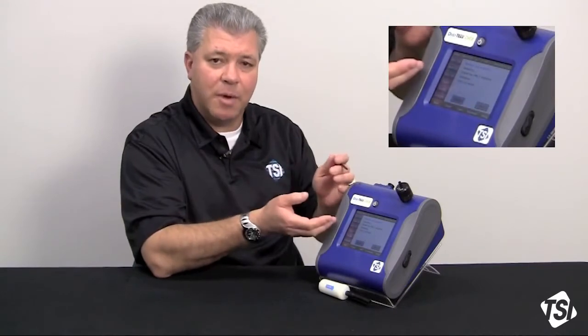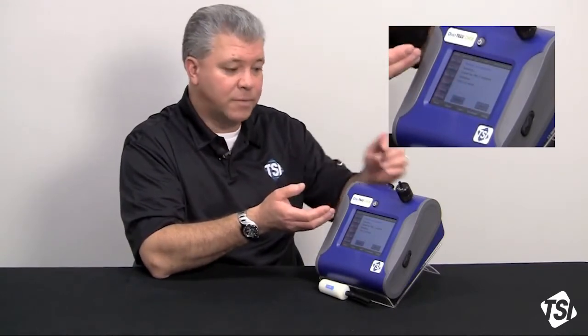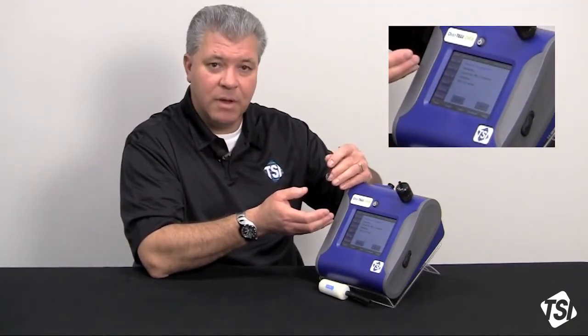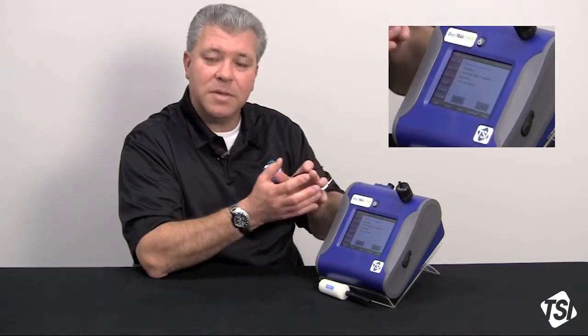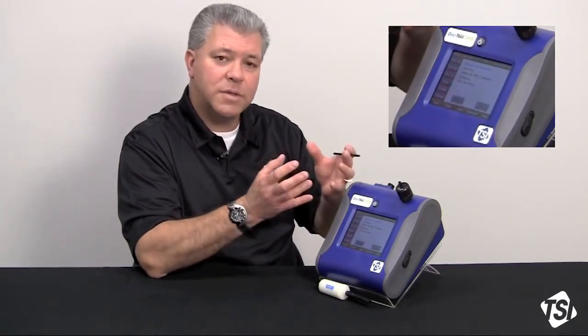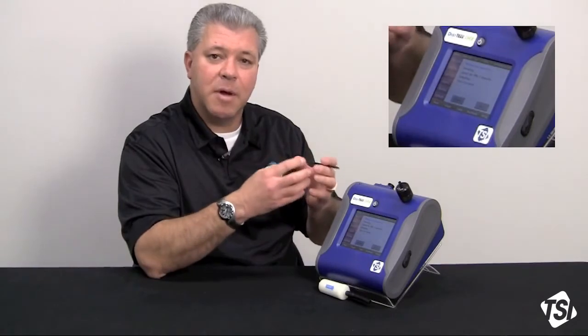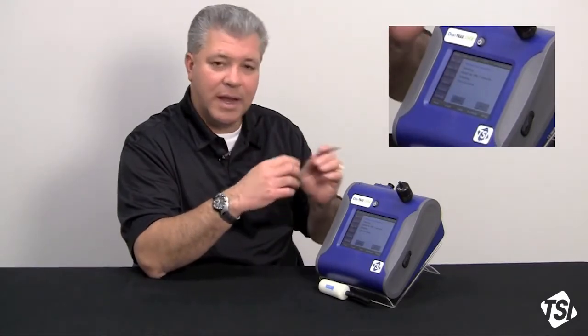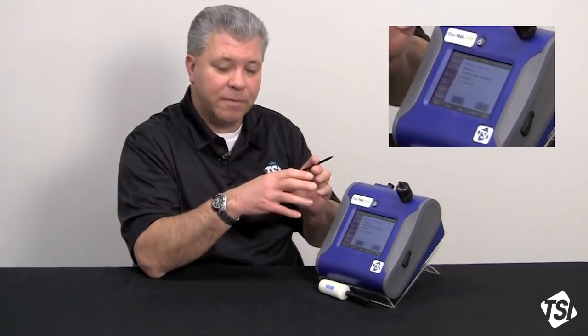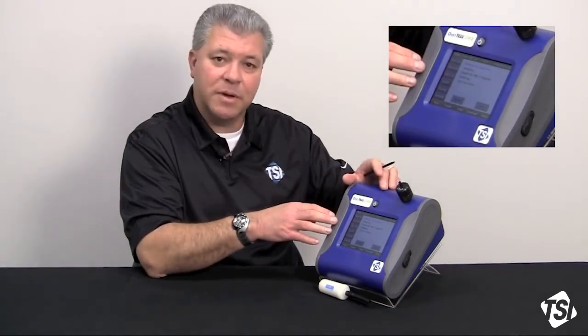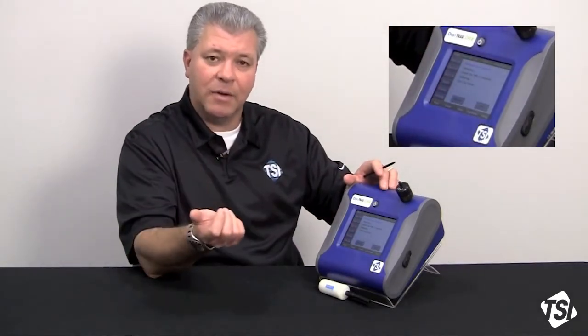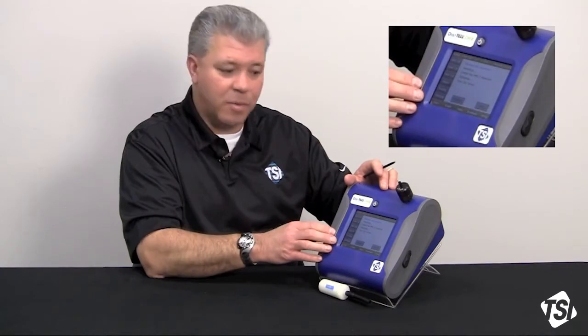It's going to take another representative sample of PM2.5 and less aerosol, down to 0.1 microns. And then it's going to compare the total versus the PM2.5, and it's going to come up with a correction factor, looking at any size distribution differences between the ambient aerosol you're measuring and the Arizona road dust that the instrument was calibrated to.